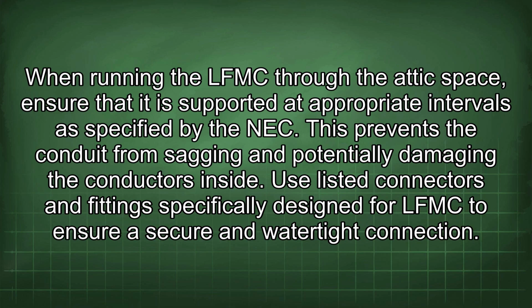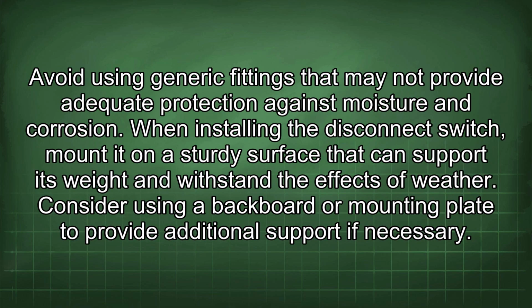When running the LFMC through the attic space, ensure that it is supported at appropriate intervals as specified by the NEC. This prevents the conduit from sagging and potentially damaging the conductors inside. Use listed connectors and fittings specifically designed for LFMC to ensure a secure and watertight connection. Avoid using generic fittings that may not provide adequate protection against moisture and corrosion.